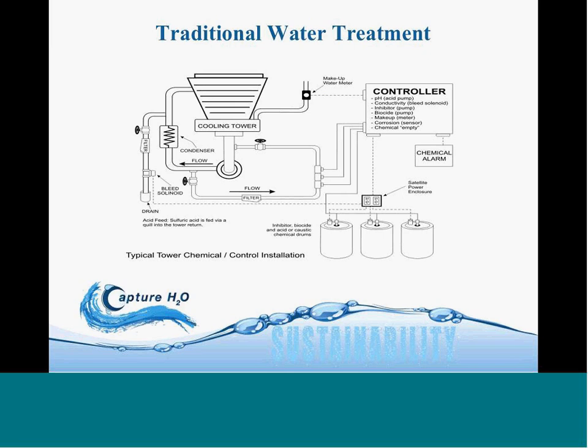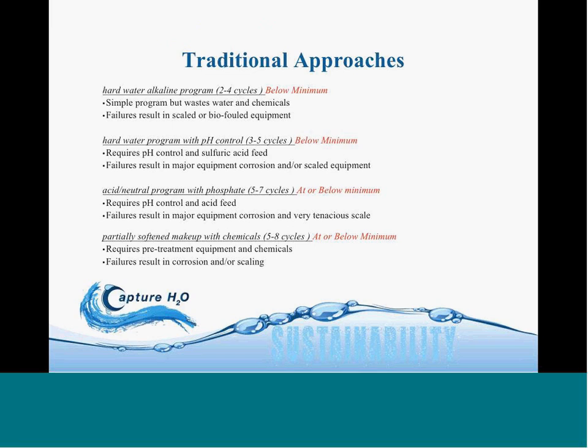So a traditional water treatment system has makeup water, evaporation, and blowdown, and you also have to pump in scale, corrosion and bacteria control chemicals. So there's a lot of moving parts and a lot of complexity to it, and a lot of water usage and water waste.